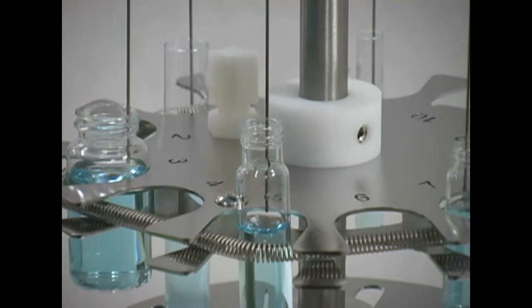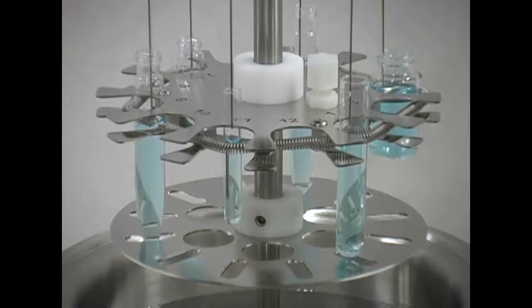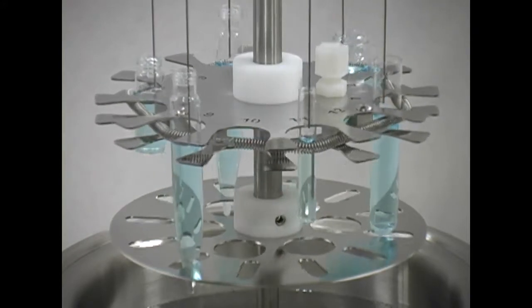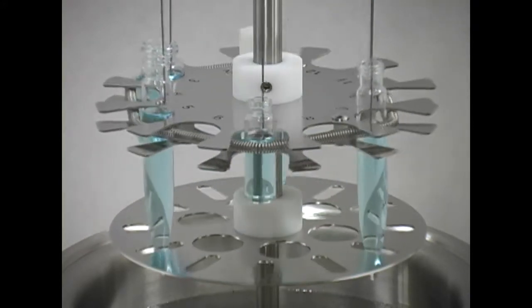Each needle is lowered until the tip is half an inch from the sample surface for optimal evaporation. The Enovap is easy to load. The sample holder rotates freely allowing all samples to be accessed from the front of the instrument.